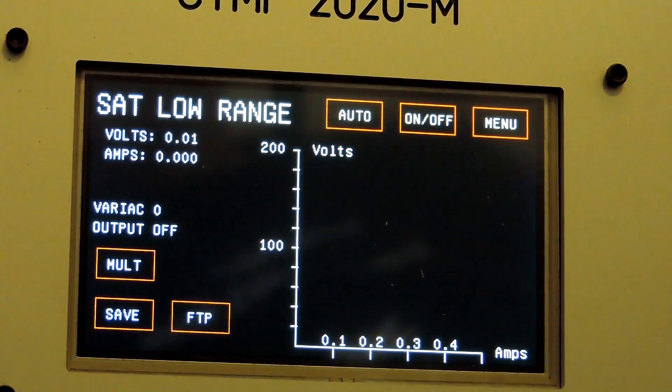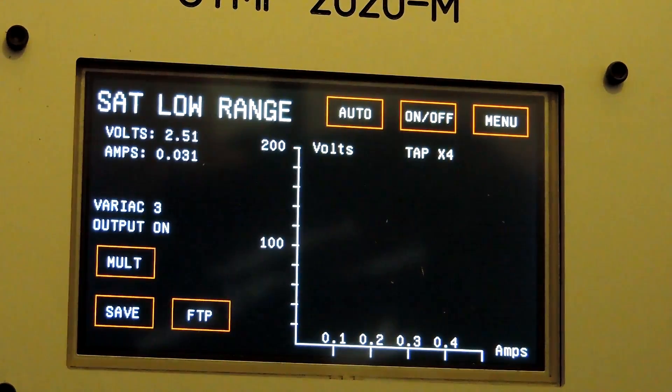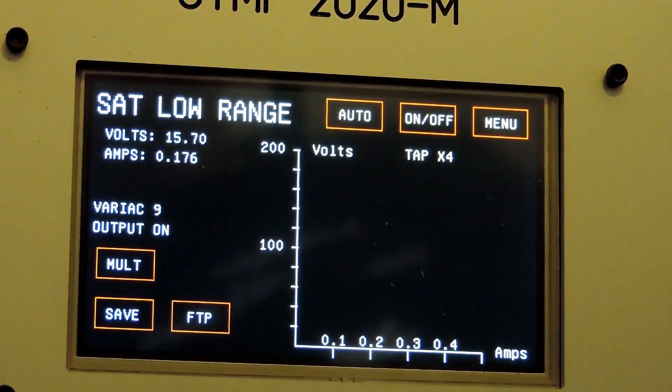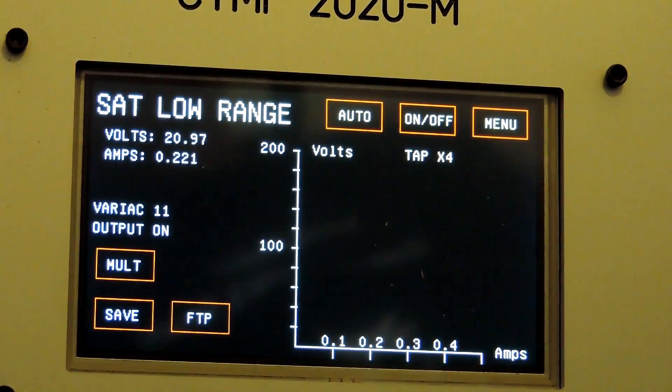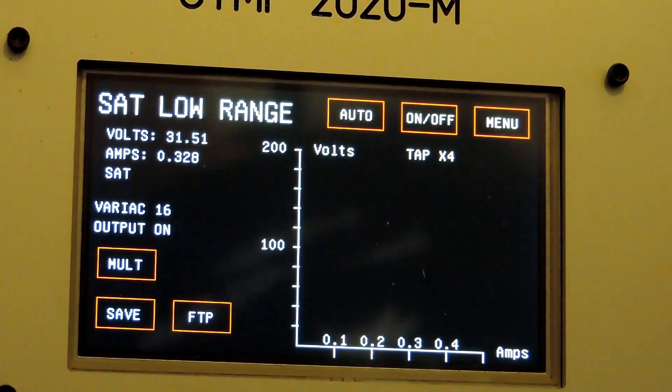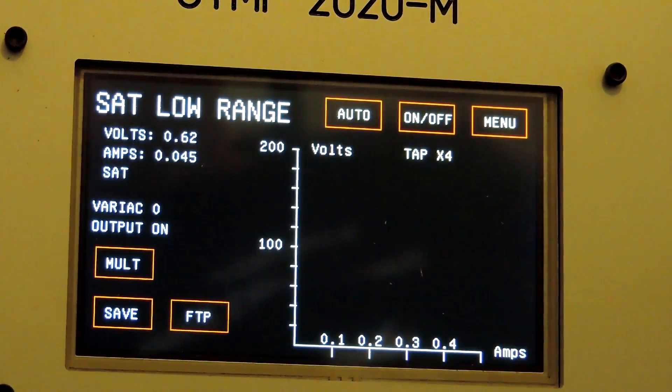Okay, erasing that and now it will proceed to test tap X4. X4 saturates really quick, it's 200 to 5, so you don't get a very good characteristic out of it.